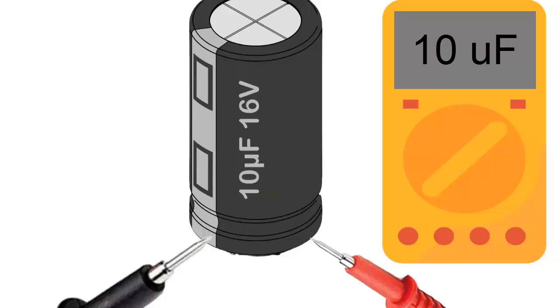If you have a capacitance meter, set it to the appropriate range. Connect the capacitance meter probes to the capacitor terminals. Read the capacitance on the display and compare it to the nominal value indicated on the capacitor.